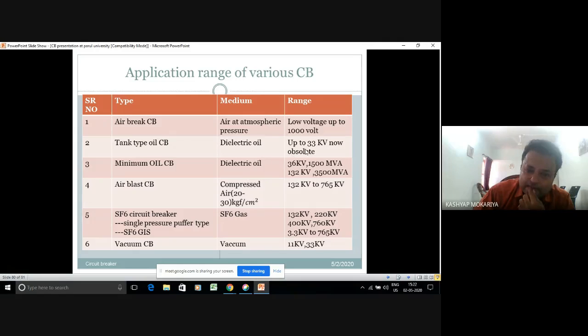Tank type breakers up to 33 kilovolt are now obsolete. Frankly speaking, in the industries which I visited, I didn't see the MOCB or BOCB, because there were maintenance issues of the minimum oil circuit breaker: the carbonization issues in the oil, the dielectric strength of the oil, the BDV check of the oil. All these issues were there in the case of these OCBs.